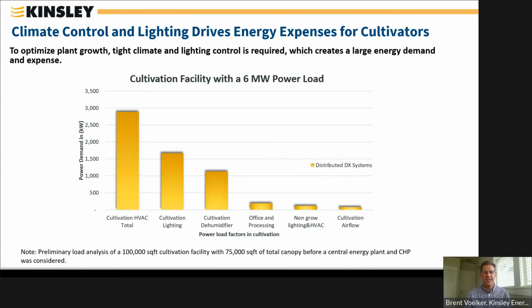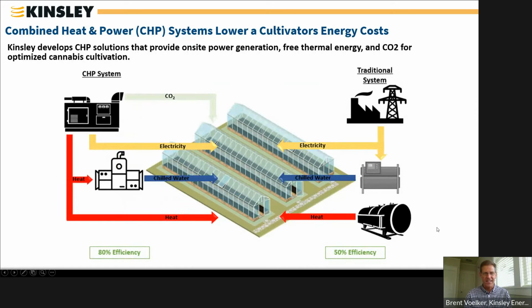So if you go to the next slide, Steve, the very simple little diagram. We didn't get very technical here at all today. We're happy to go into much more detail with you in the future, but this shows you what a CHP system basically can do. On the right-hand side, we've got traditional utility power, providing electricity, chilled water for cooling and dehumidification, and heat for reheat. Very often, your system will subcool the air in order to dehumidify, and then you need to reheat before the air goes back into the room.